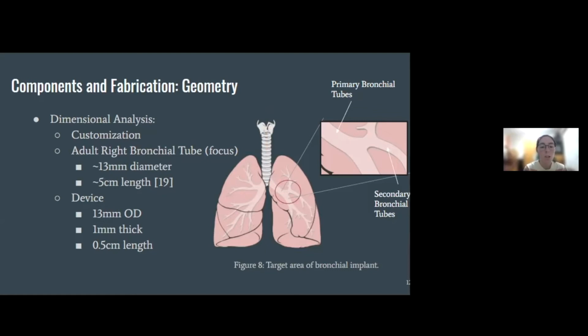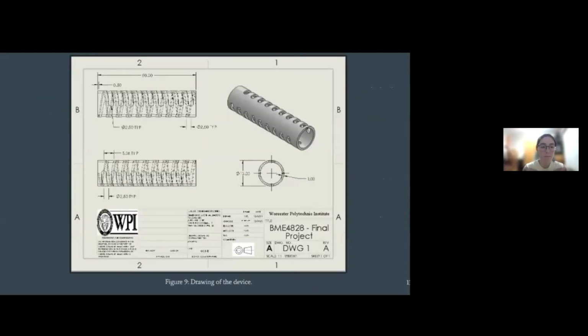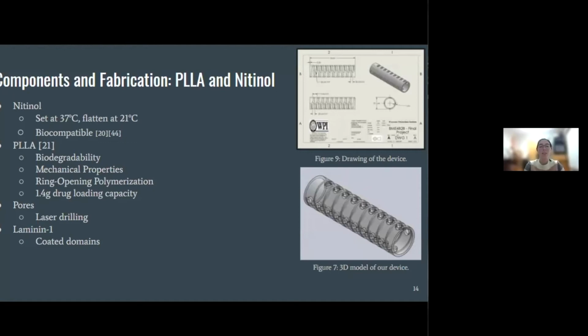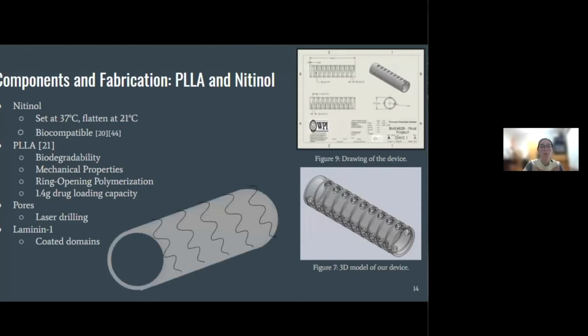The stent's geometry will be patient-specific, based on MRI analysis. In general, the device will be around 13 millimeters in outer diameter, 1 millimeter thick, and 0.5 centimeter long. This is a drawing of our device. The nitinol mesh is embedded in a polymer shell to mitigate migration through mechanical loading on the surrounding endothelial tissue. The nitinol is mechanically polished to increase corrosion resistance.